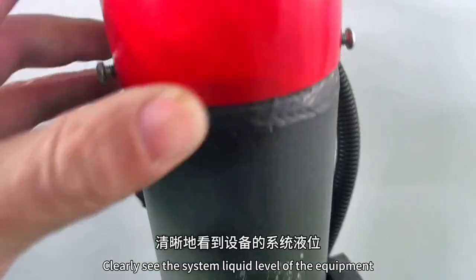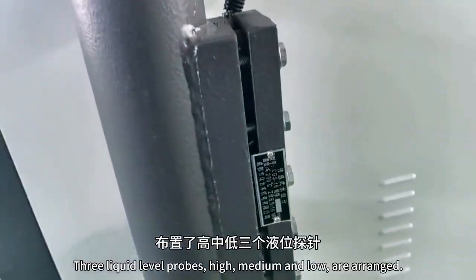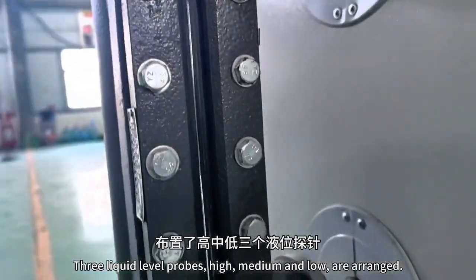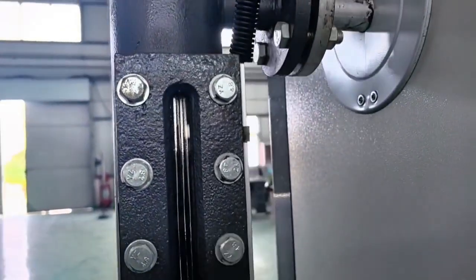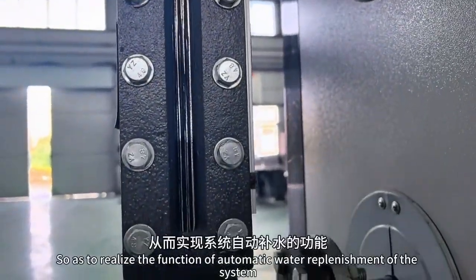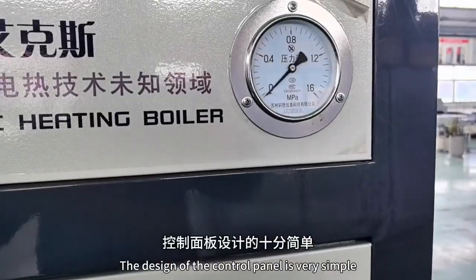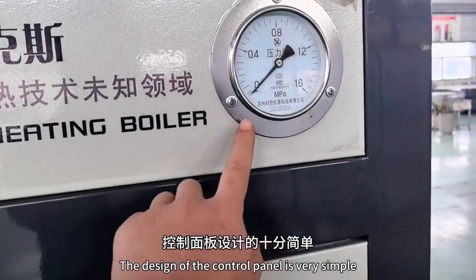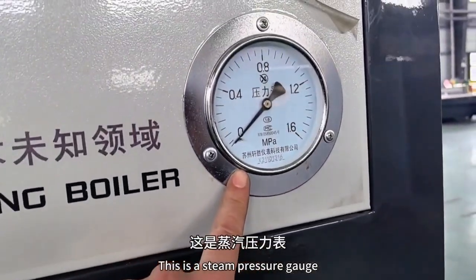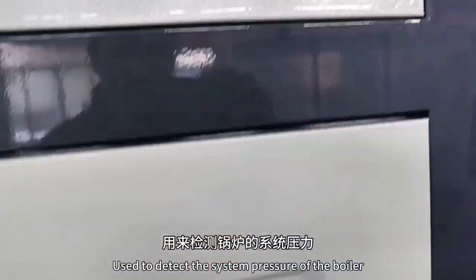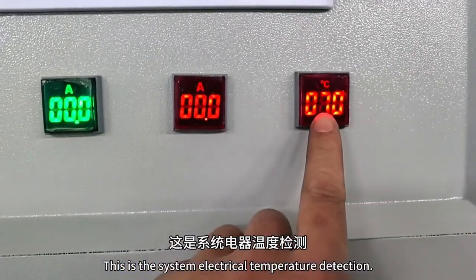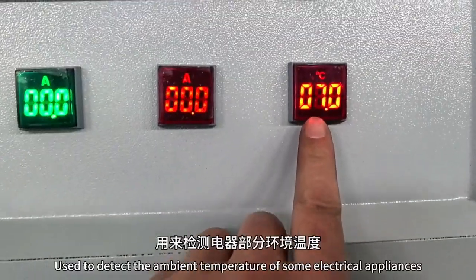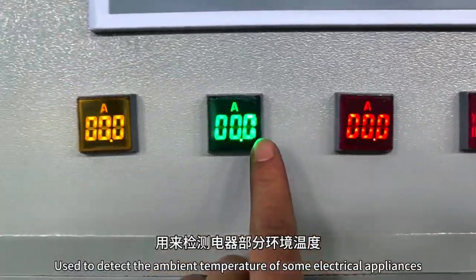This is a liquid level detection device, which can clearly show the system liquid level of the equipment through a glass mirror. Three liquid level probes, high, medium, and low, are arranged inside for liquid level detection, thus achieving the automatic water replenishment function of the system. The control panel design is very simple. This is a steam pressure gauge used to detect the system pressure of the boiler.